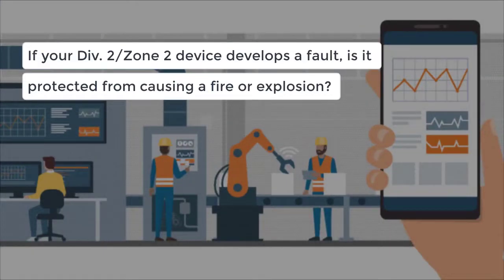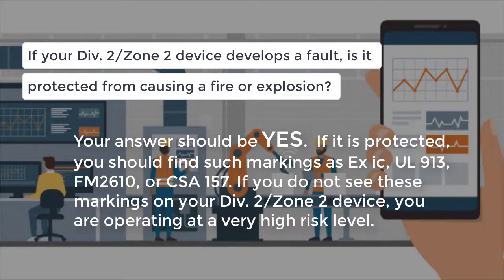If your Zone 2 or Division 2 device develops a fault, is it protected from causing a fire or explosion? Your answer should be yes. If it is protected, you should find such markings as Ex ic, UL 913, FM 2610, or CSA 157. If you do not see these markings on your Zone 2 or Division 2 device, you are operating at a very high risk level.